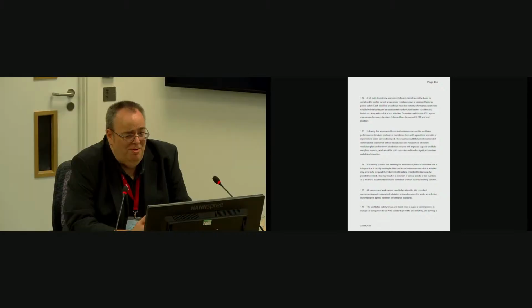It's very difficult to say that the existing system is adequate when it doesn't meet the current stated minimum standards. Now, if adequate mitigation is provided and the multidisciplinary risk assessment states that they are safe and appropriate, that would be fine. But from a ventilation perspective, I stand by my position that they are currently suboptimal.